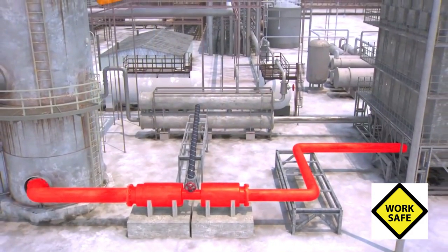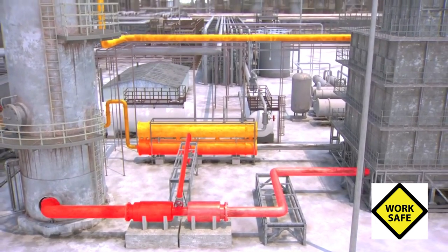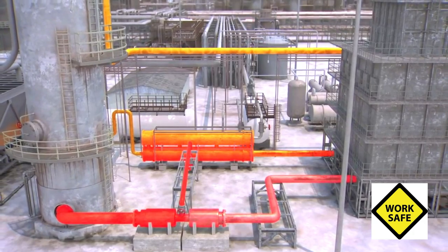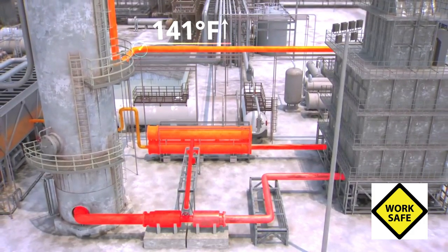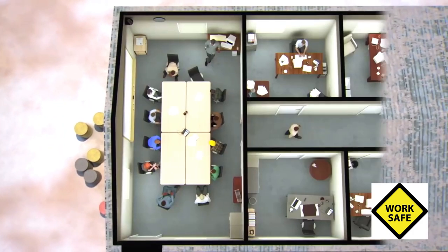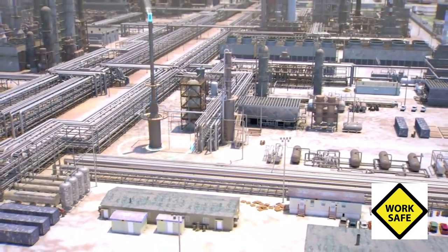The operators did become concerned about the lack of flow out of the tower and began opening the valve to send liquid from the bottom of the tower to storage tanks. But this liquid was very hot. As it flowed through the heat exchanger, it suddenly raised the temperature of the liquid entering high up the tower by 141 degrees Fahrenheit. It was now about 1 p.m. Contract workers, unaware of the start-up and the looming danger, returned from lunch and began a meeting in the double-wide trailer, in the corner room closest to the blow-down drum.